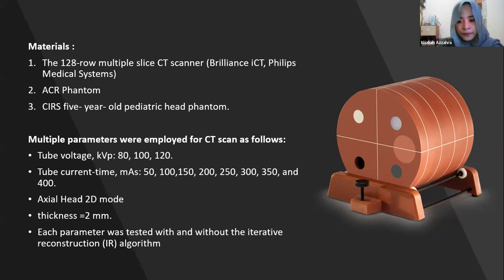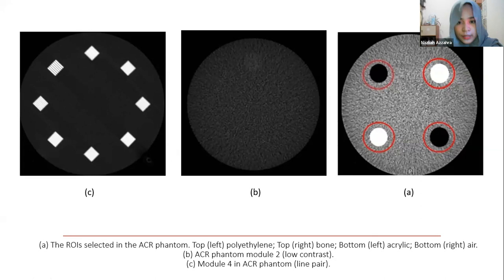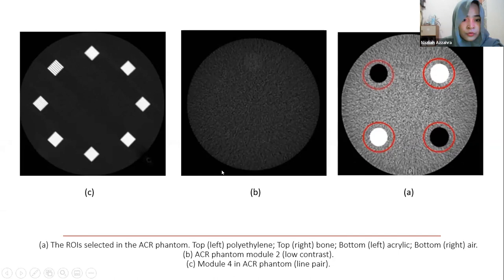The ACR phantom is equipped with four modules, but in this study we will only use modules one, two, and four. Module one assesses CT number accuracy — the cylinder houses five different materials: polyethylene, bone, acrylic, air, and a water-equivalent background. Module two assesses low contrast resolution; a 25-millimeter cylinder is used to verify the cylinder-to-background contrast level. Module four assesses high contrast or spatial resolution.